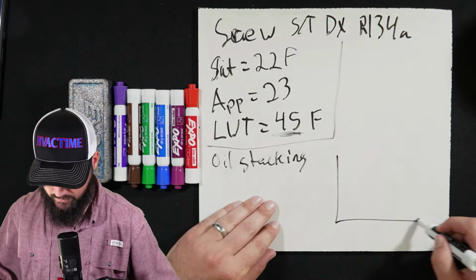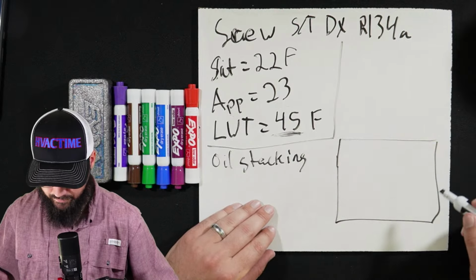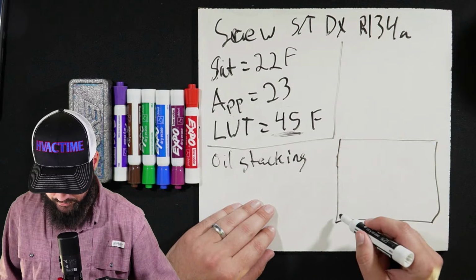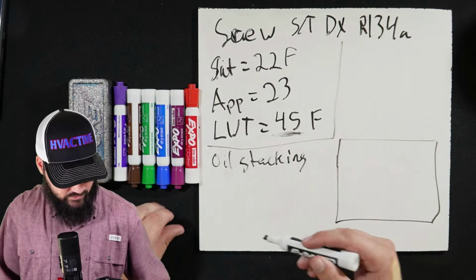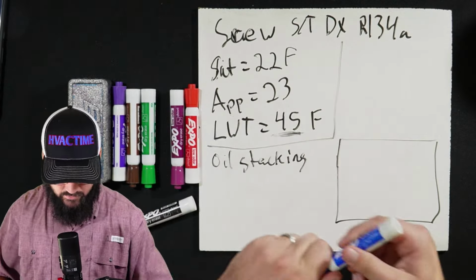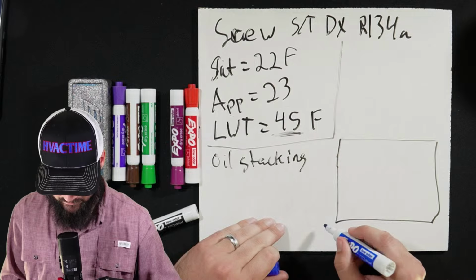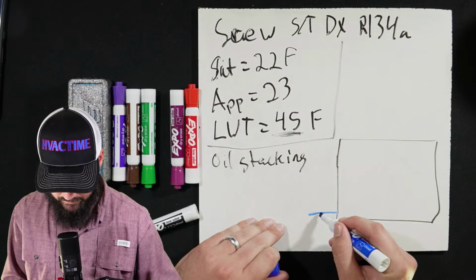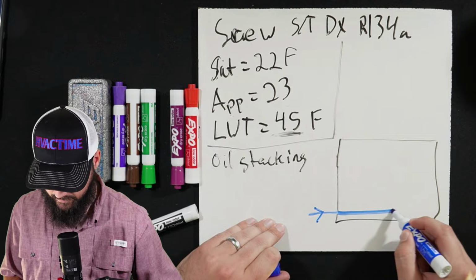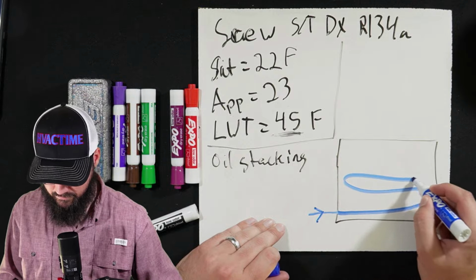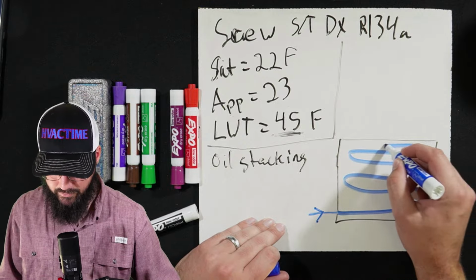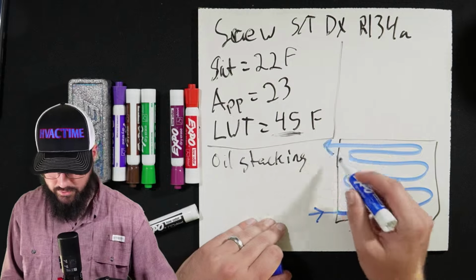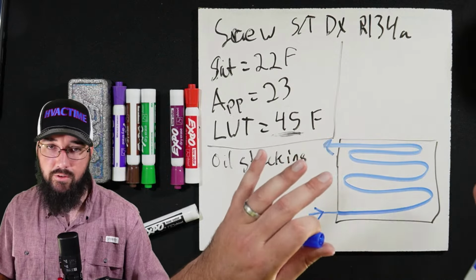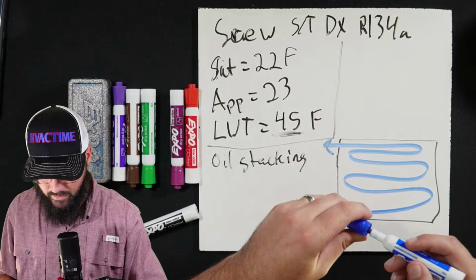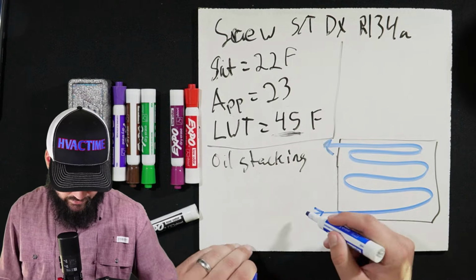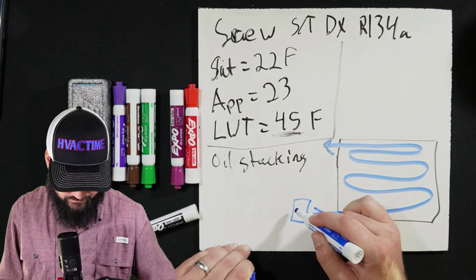Let's say this is our evaporator, and then our tubes here. We have our refrigerant entering here at the bottom. We're going to come up through the evaporator, and then we're going to come out the suction on the top of it. So this would be a standard shell and tube DX design. Metering device would be right here. Okay.